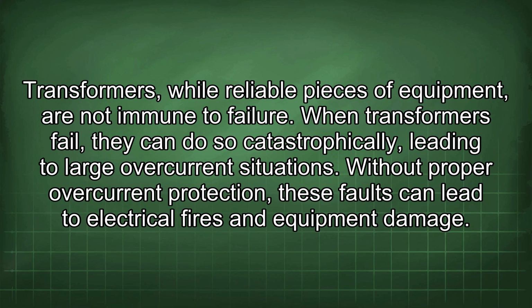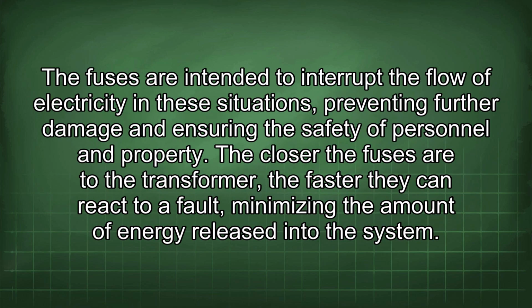Without proper overcurrent protection, these faults can lead to electrical fires and equipment damage. The fuses are intended to interrupt the flow of electricity in these situations, preventing further damage and ensuring the safety of personnel and property. The closer the fuses are to the transformer, the faster they can react to a fault, minimizing the amount of energy released into the system.